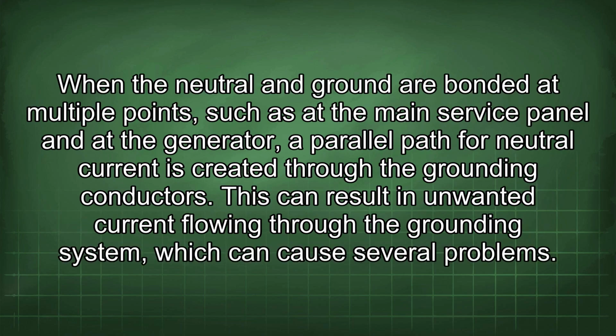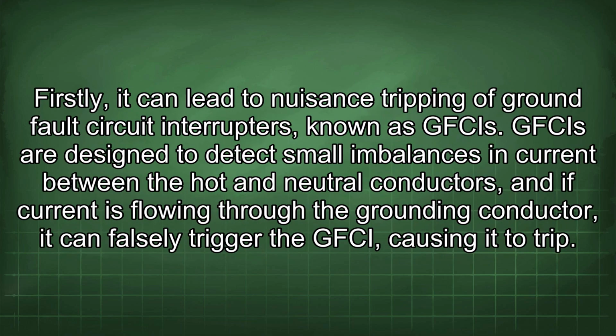When the neutral and ground are bonded at multiple points, such as at the main service panel and at the generator, a parallel path for neutral current is created through the grounding conductors. This can result in unwanted current flowing through the grounding system, which can cause several problems. Firstly, it can lead to nuisance tripping of ground fault circuit interrupters, known as GFCIs. GFCIs are designed to detect small imbalances in current between the hot and neutral conductors, and if current is flowing through the grounding conductor, it can falsely trigger the GFCI, causing it to trip.